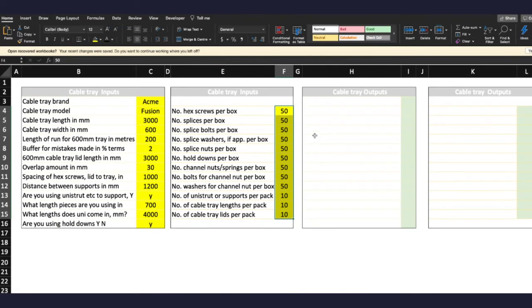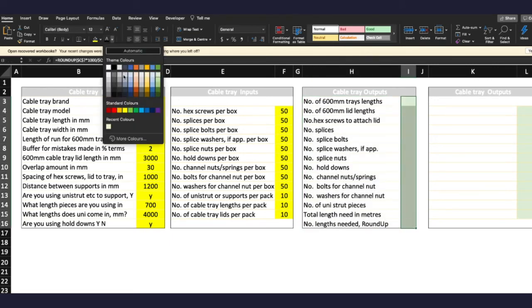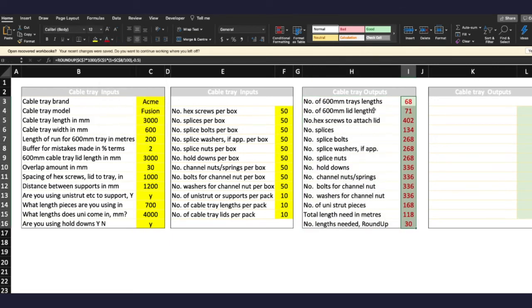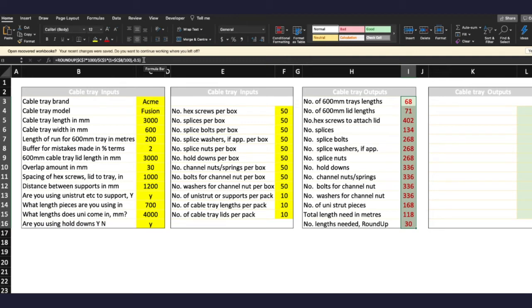Now for the most important, or equally as important, cable tray outputs. This is where the calculations go on. So number of 600 millimeter tray lengths is 68, and the length is 71. And obviously the length is going to be, you're going to have more lengths than the actual lid than you have the tray because you've got an overlap. Now of course these calculations, as you can see here, they round up and you must always round up when it comes to sections of tray or rail or lid or something that you put together to create a particular run.